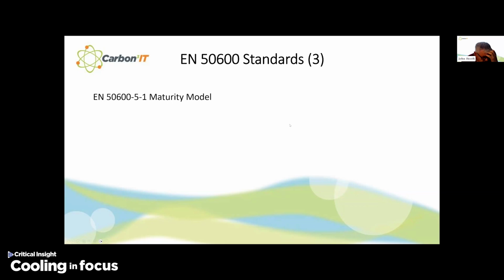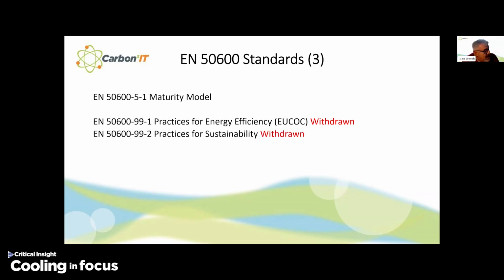Now, there is also one that, if you haven't got a copy of, I would advise everybody to go out and purchase one. It's available on our website. 50600-5-1, the maturity model. This includes the best practices that were originally called TR 50600-99-1, practices for energy efficiency, which is basically the standardized version of the Code of Conduct. You can buy the Code of Conduct, but you can get the Code of Conduct free. And also the practices for sustainability. Those have both been withdrawn because most of the best practices have now been incorporated into the 5-1 standard maturity model. There is also the 99-3, which is the guidance to the application of the 50600 series.